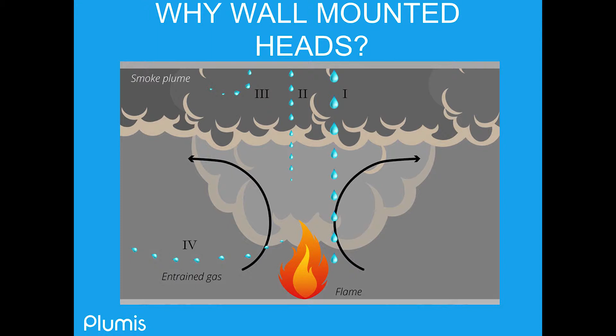We all remember a concept of Archimedes. We're not going to go into too much fire dynamics and physics today, although I would love to talk with my fellow fire protection engineer about it. The whole concept here is a sprinkler head is up on the top of this depiction here. That's where the hot layer is. That's what we've been talking about. That is how sprinkler heads actually deploy. It gets hot, it either breaks a bulb or some other mechanism, and then the water flows from the pipe through that. It tends to be a large droplet. It has a lot of mass. It comes down through and wets an area of the floor. There are some losses, obviously, if it's going through all the heat, it's water, it's cooling that upper layer. That's a good thing, and the rest of it comes down and goes to the fire.